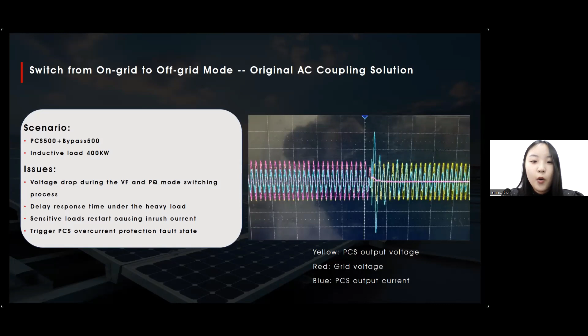See the second one, when the grid failed and the battery was powering the loads, but the battery is not inexhaustible. When the battery capacity is about to reach the SOC limit, now the system needs to switch to diesel generator working mode. But due to the weak generator performance, diesel generator mode triggers a voltage drop. Check this pink line. And you might ask, I thought the pink line is normal after it dropped.